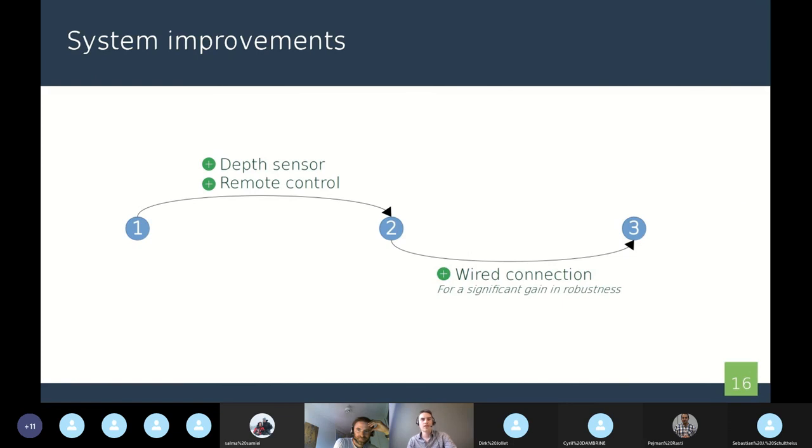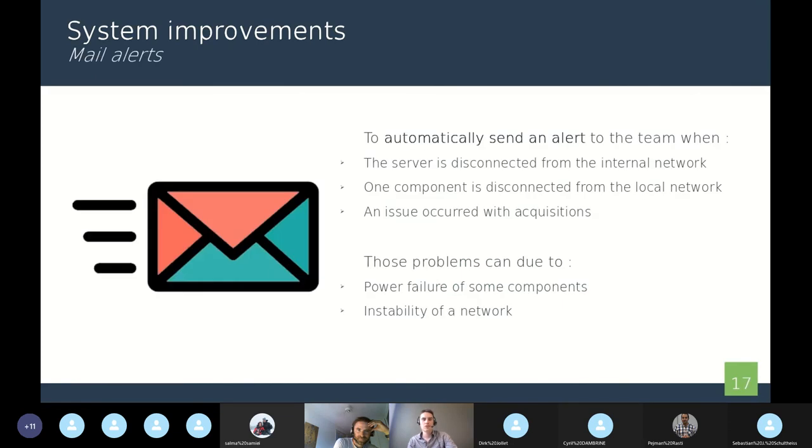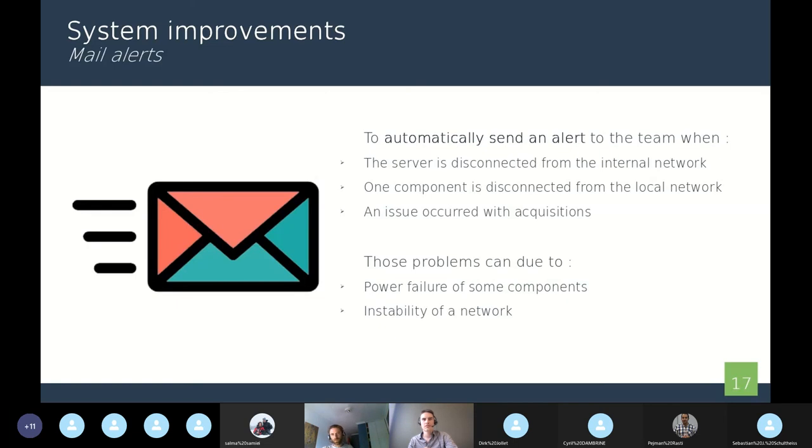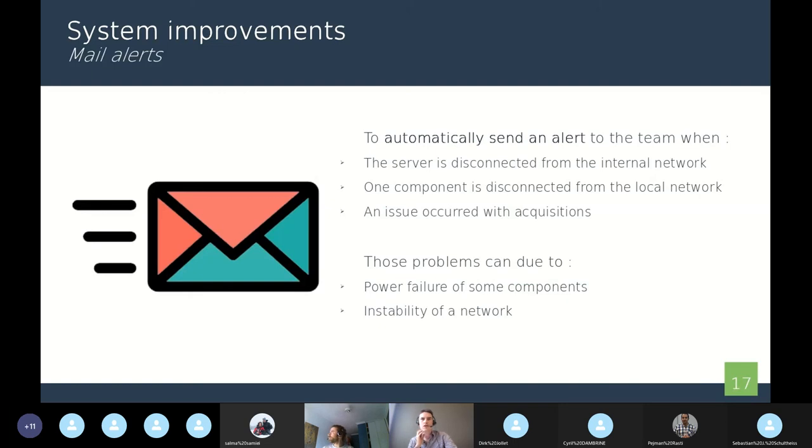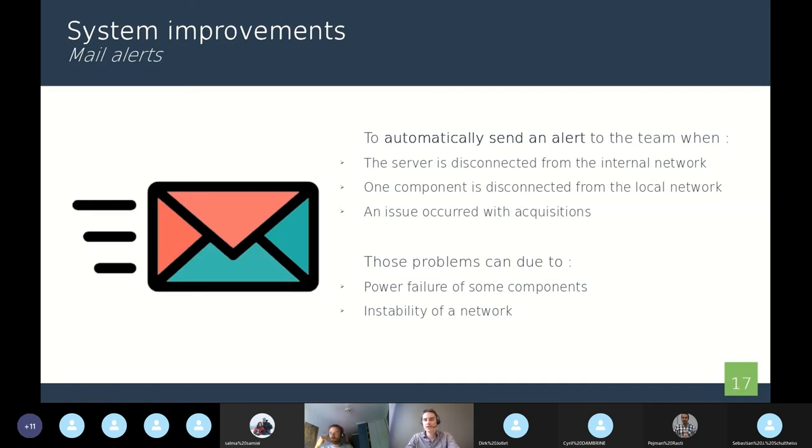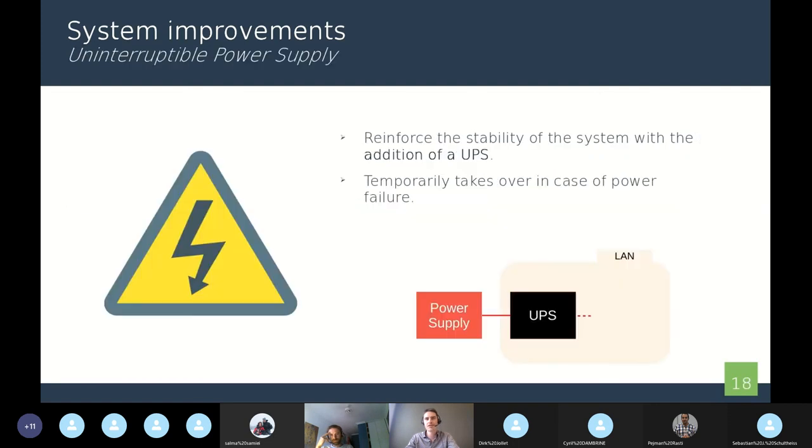Now I can talk about the systems of mail alerts. These systems send an alert explaining what and where is the issue in the network. It can be a disconnection of the server, a disconnection of another component, or an issue with some acquisitions. The problem of disconnection might be due to power failures or just instability of the network, especially in a wireless system. Because in greenhouses, the environment can be really noisy and we can have a very big instability of the network.